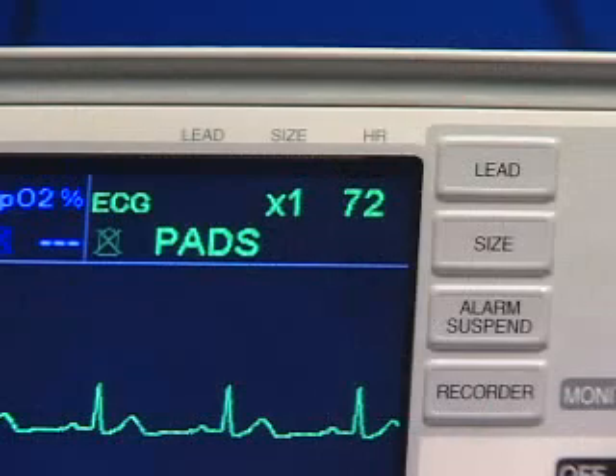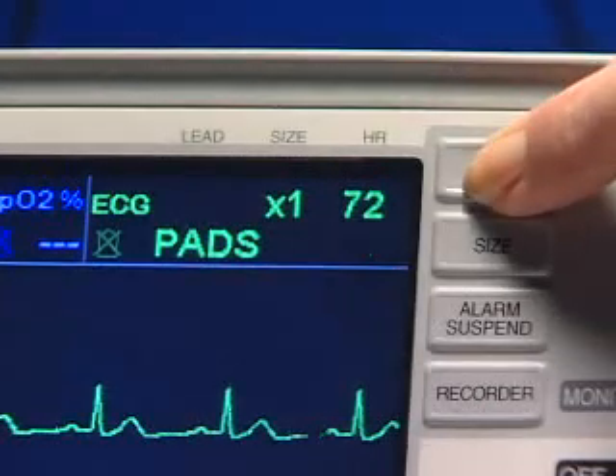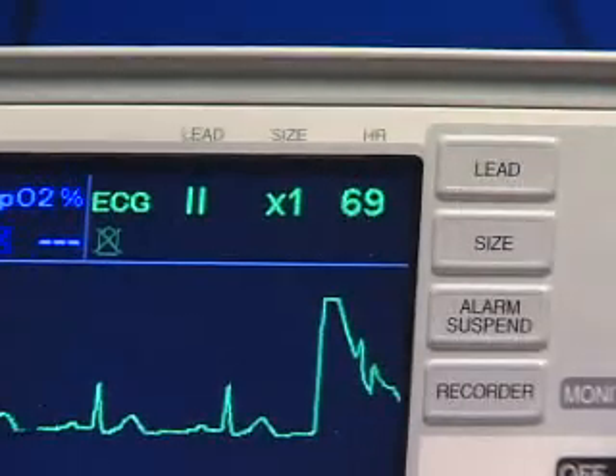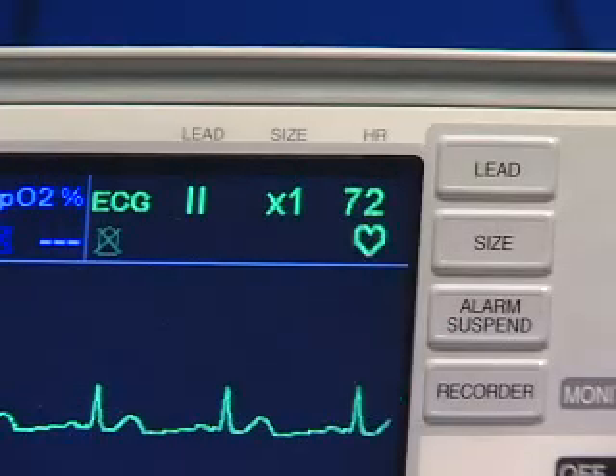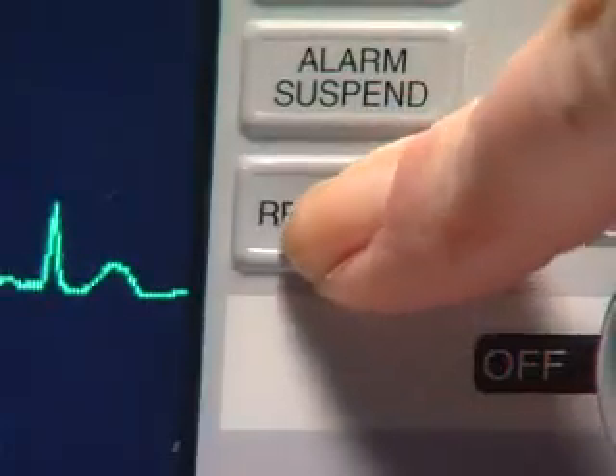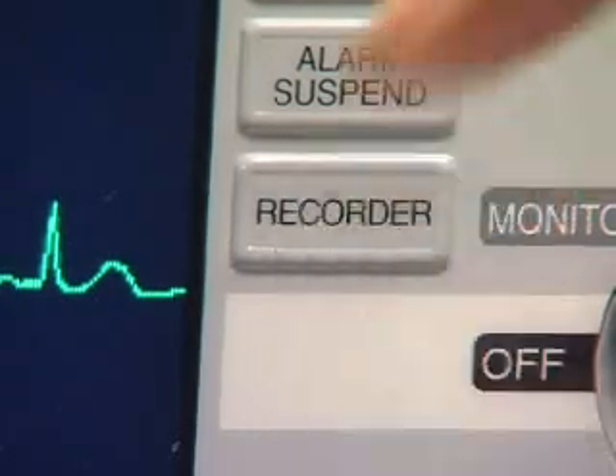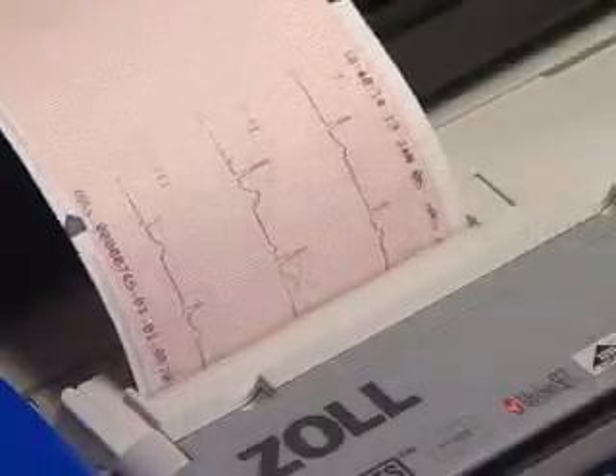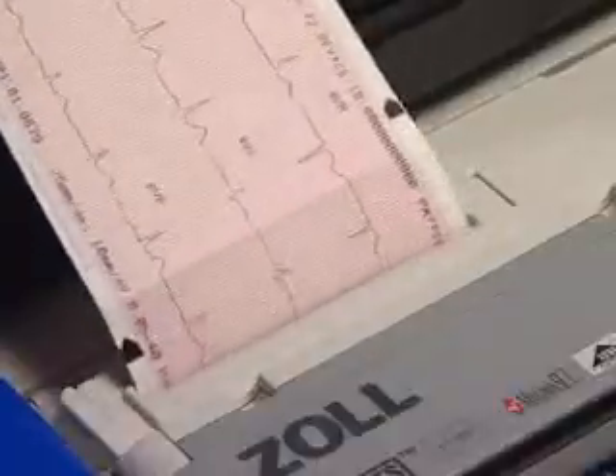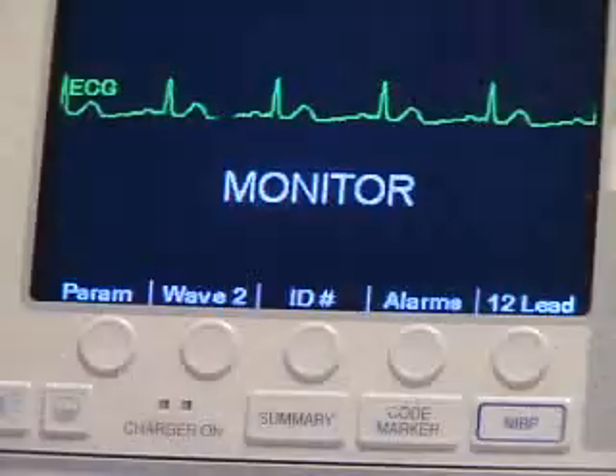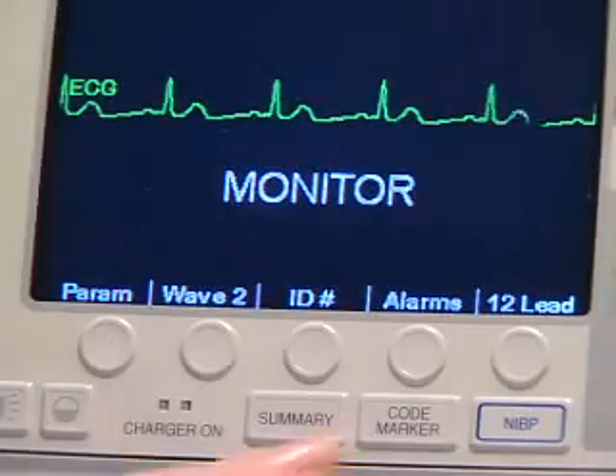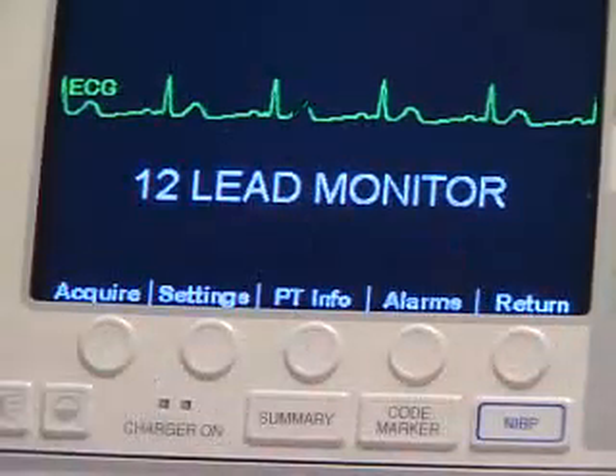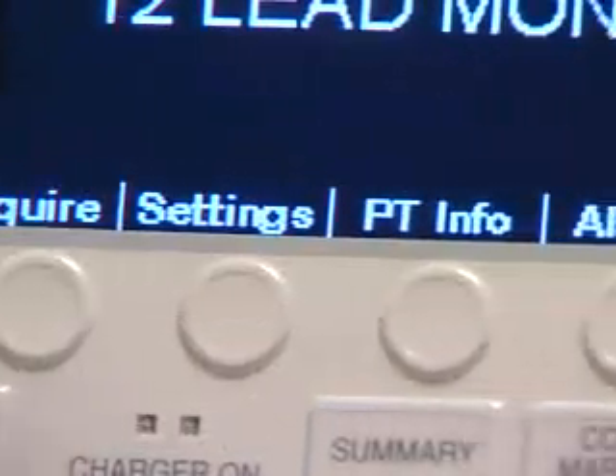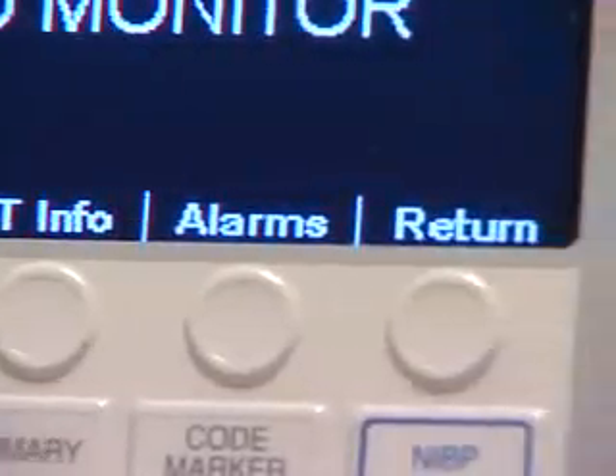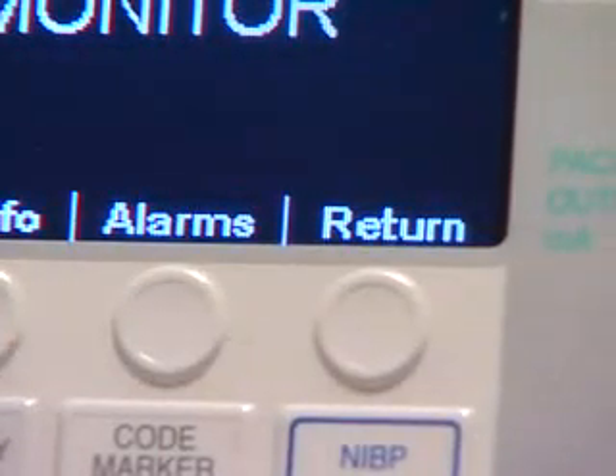Turn the selector switch to Monitor. If a PADS or paddles message is displayed, select a lead. You must select a lead to obtain the 12-lead ECG report. To print a 12-lead report only, press and hold the Recorder button for 3 seconds. A 4x3 12-lead report without interpretation will be printed. When the 12-lead soft key is pressed, the following soft keys will be displayed: Acquire, Settings, Patient Info, Alarms, and Return.